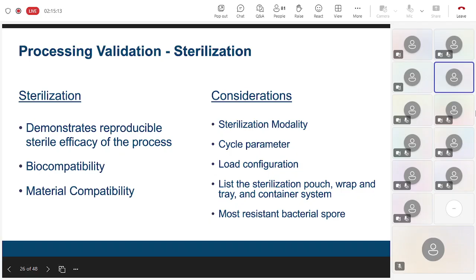Also, the sterilisation process should identify the sterilisation barrier systems and their accessories. So the sterilisation pouch materials and size, the wrap, the weight, the tray that is going to be used to hold the device, the container systems and the filter models used. Each sterilisation process kills and inactivates bacterial spores differently, so it may be necessary to validate all of the consumables that you use when you are validating these cycles of sterilisation for 3D printed medical devices.